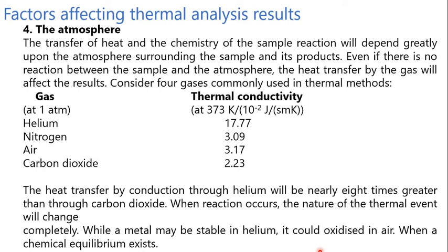So that's why the atmosphere plays an important role in thermal analysis. Even if there is no reaction between the sample and atmosphere, the heat transfer by the gas will affect the results. Consider four gases commonly used in the thermal methods, that is helium, nitrogen, air and carbon dioxide. Their thermal conductivities are: helium 17.77, nitrogen 3.09, air 3.17 and carbon dioxide 2.23.